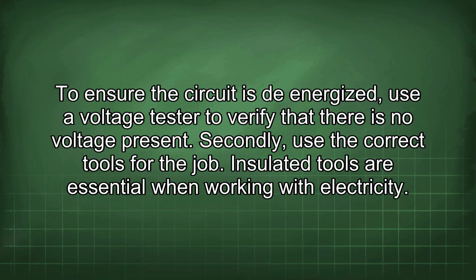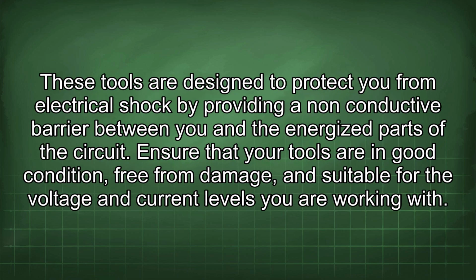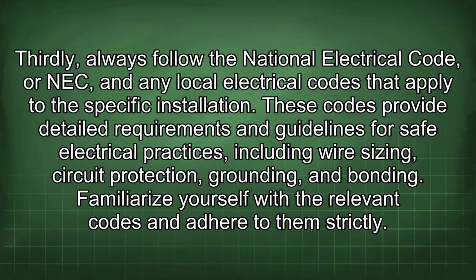Insulated tools are essential when working with electricity. These tools are designed to protect you from electrical shock by providing a non-conductive barrier between you and the energized parts of the circuit. Ensure that your tools are in good condition, free from damage, and suitable for the voltage and current levels you are working with. Thirdly, always follow the National Electrical Code, or NEC, and any local electrical codes that apply to the specific installation. These codes provide detailed requirements and guidelines for safe electrical practices, including wire sizing, circuit protection, grounding, and bonding. Familiarize yourself with the relevant codes and adhere to them strictly.